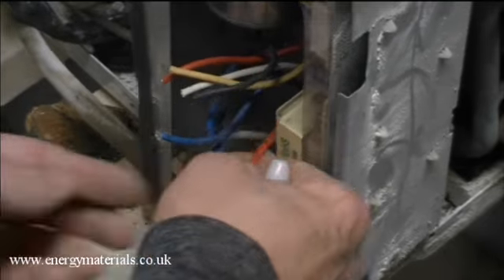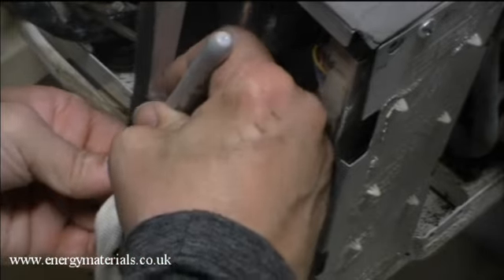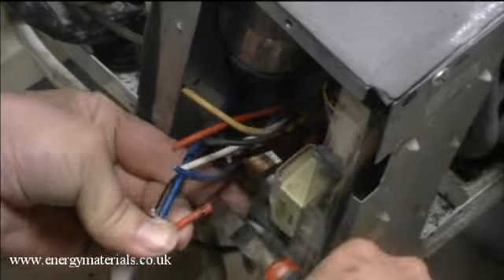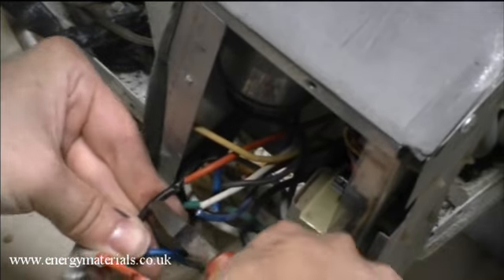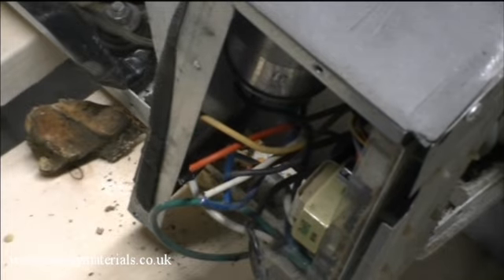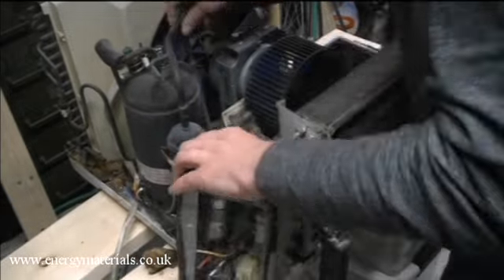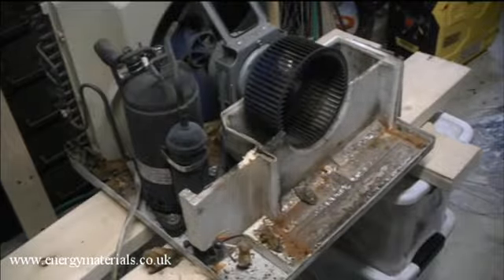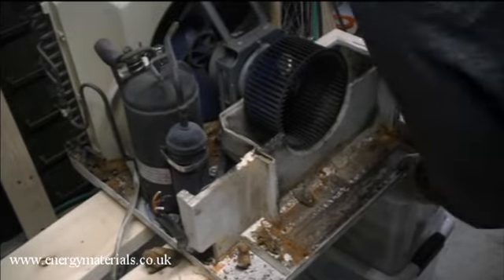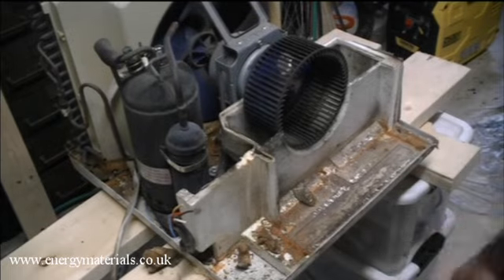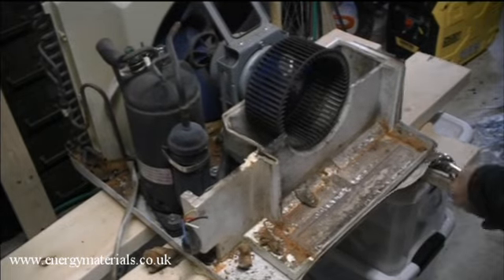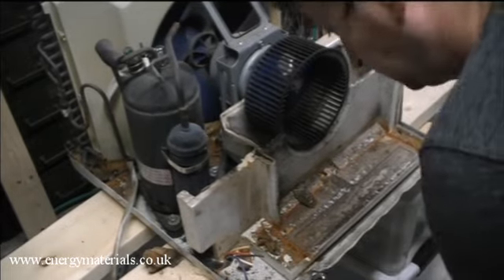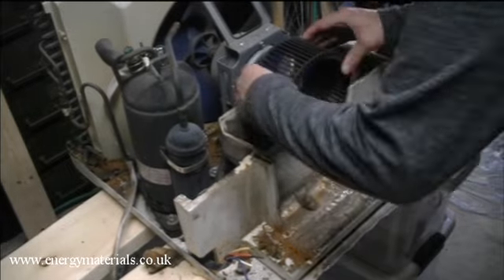Now disconnecting the control panel, marking wires, just in case I need to reuse them. And now hopefully I can remove the evaporator. Yep. So there's a lip in front which is preventing me from removing the lower cowling and the radial fan. So a little bit of modification, and yep, we've got that off.